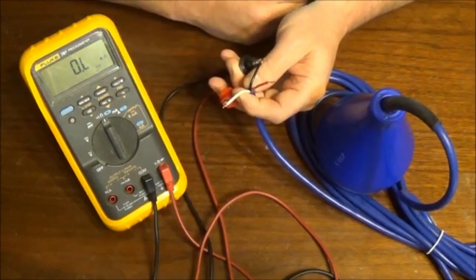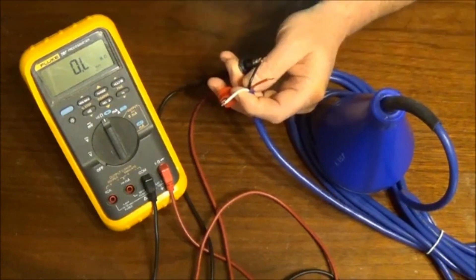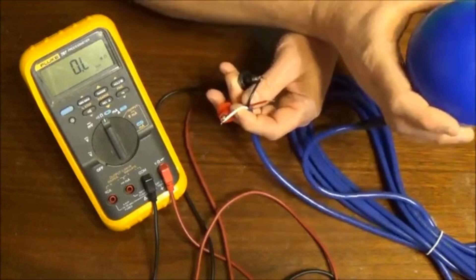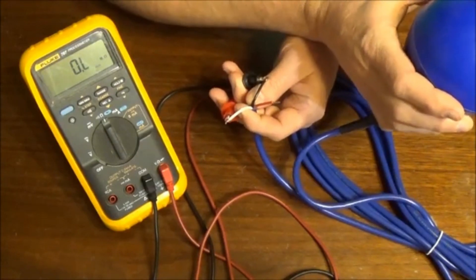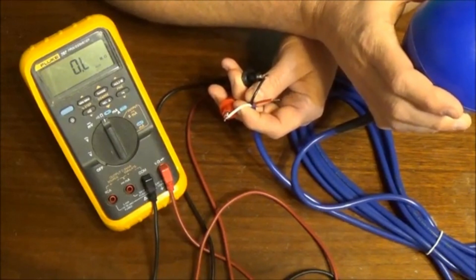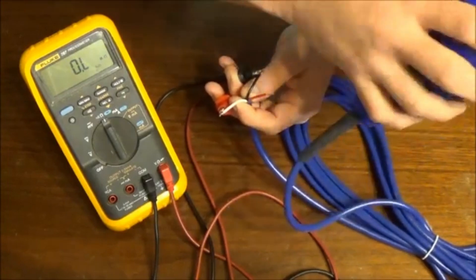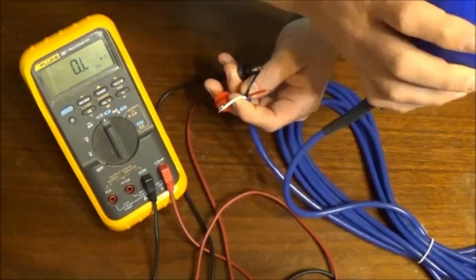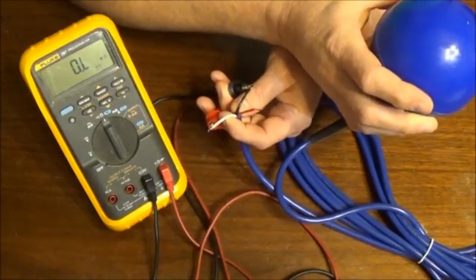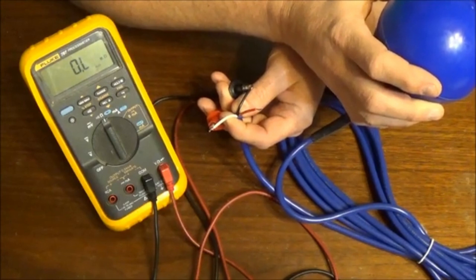Let's say that it is. So now we've got the leads measured across the float. And if we toggle the float to what should be the other condition or opposite condition, that state should change to a short. As you can see, you can hear the switch toggling. This meter is reading the same either way, indicating that the float switch is bad.